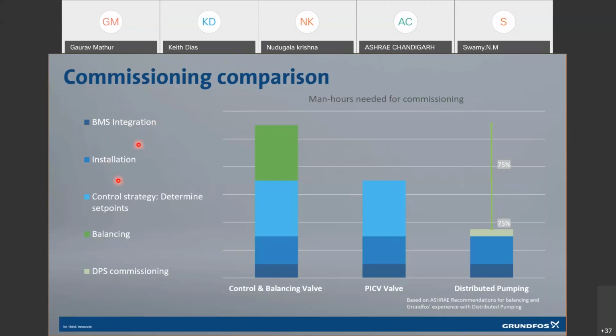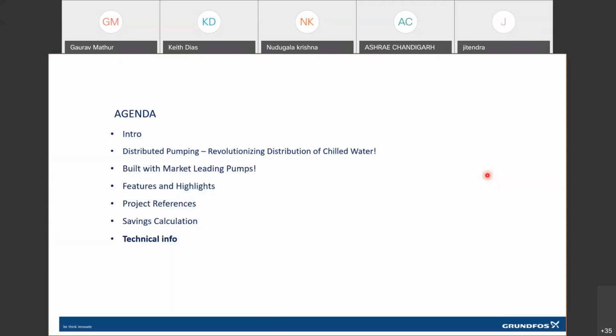The installation is much easier because the moment you install a pump, you have the entire controls, the sensors, the intelligence, everything inbuilt. So you need not do complex programming to commission the system. And then in terms of control strategy and balancing, overall, in terms of man hours, you see an improvement of around 75% based on our experience in the site commissionings which we have done.